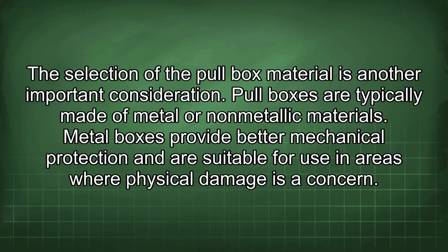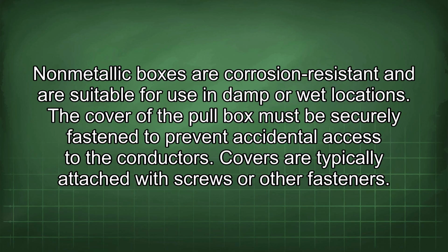The selection of the pull box material is another important consideration. Pull boxes are typically made of metal or non-metallic materials. Metal boxes provide better mechanical protection and are suitable for use in areas where physical damage is a concern. Non-metallic boxes are corrosion resistant and are suitable for use in damp or wet locations. The cover of the pull box must be securely fastened to prevent accidental access to the conductors.